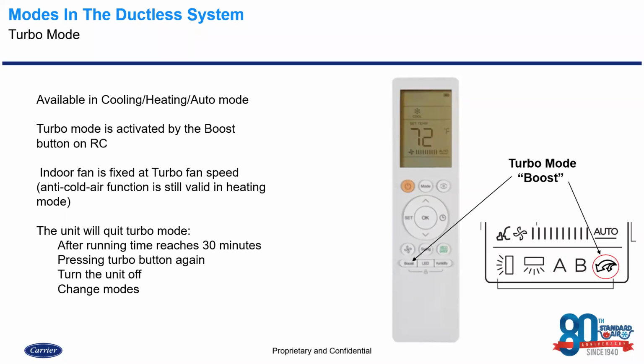Okay, if it can't reach that set point in 30 minutes, it doesn't throw an error code. It just goes back to the original set point, fan speed, and configuration that you had prior to entering turbo mode. So turbo mode is essentially focused on the sensible load and not the latent load.